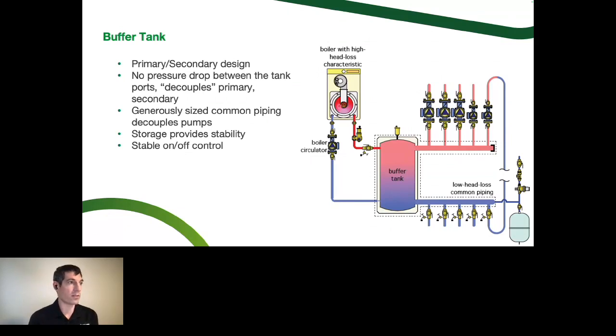So we need to make sure that we're setting up the new equipment for a long service life. We want to make sure that we've got some buffer capacity so it can have a 30-minute run cycle or whatever we design there. So a buffer tank is just a supersized hydro separator. This is just a big open vessel here that's going to give us a big thermal battery to charge up. And then it's such a big wide open lake of water in here that the pressure drop is minimal for the supply to come back to the return here. So it still works well to be a primary secondary device. It's just the biggest, most expensive version because it's a pressure vessel that's going to be insulated versus two copper tees that you could pick up at a wholesale counter or something like that.